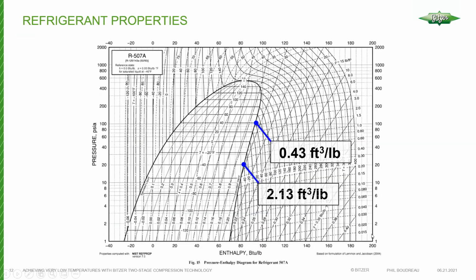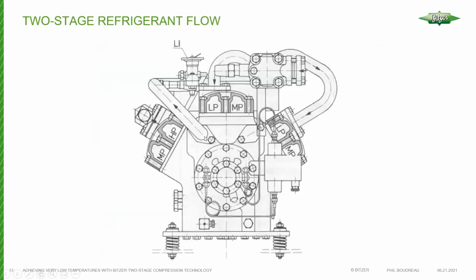So you may be wondering, why do we have more cylinders in the low stage versus the high? Well, it's very basic in principle. If you consider the specific volume of a refrigerant, and I just picked 2 arbitrary values here, -40 and +40. At -40, specific volume of the refrigerant is 2.13 cubic feet per pound, and the refrigerant takes up much less space at the higher SST because the pressure is higher. So as you're compressing the refrigerant, each pound takes up less space, so we require less compressor displacement in the high stage to handle the overall mass flow.